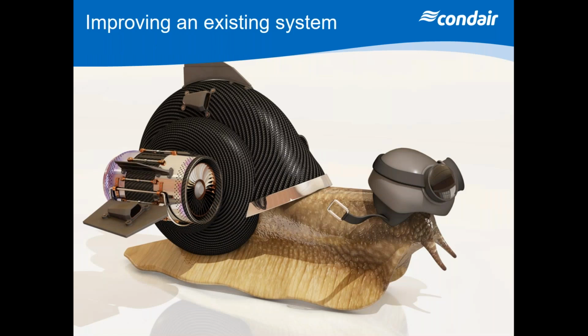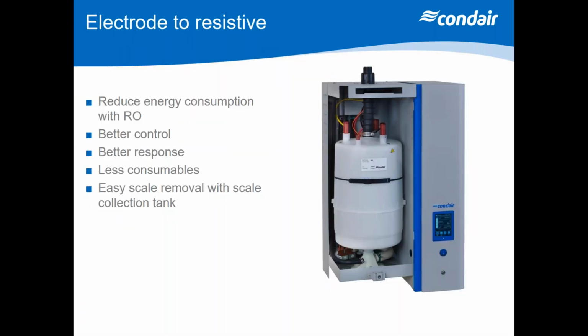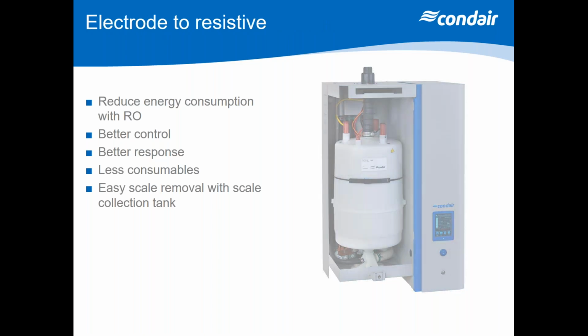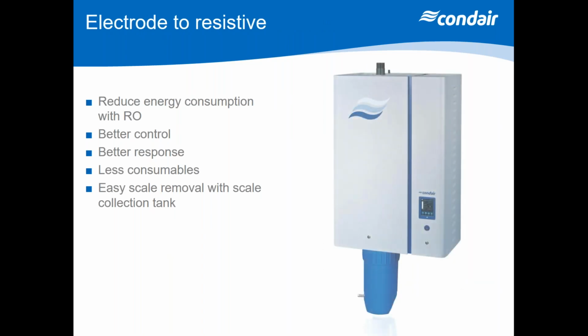So, final stretch now, improving on a system. If you were to try and replace an electro boiler with a resistive humidifier, if you run it with RO, as I said before, you're going to take out all the solids and you're going to get better control, better response, and fewer consumables than you would have with an electro boiler. And the scale management side of things is a lot easier to cope with, a lot less worrying about the expensive 400-pound cylinders. So this is something you can look at. If you've got facility for RO, it's even better to work with an electro boiler to change to resistive.